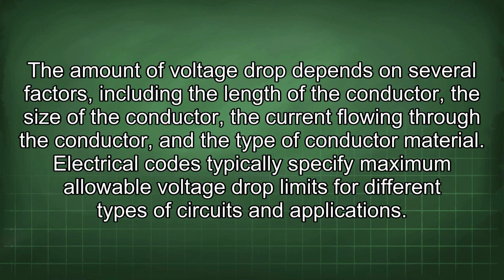The amount of voltage drop depends on several factors, including the length of the conductor, the size of the conductor, the current flowing through the conductor, and the type of conductor material. Electrical codes typically specify maximum allowable voltage drop limits for different types of circuits and applications.